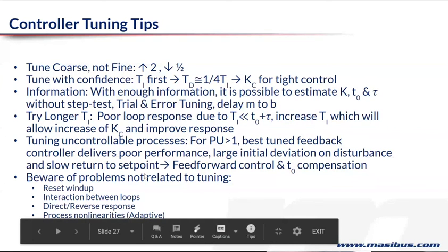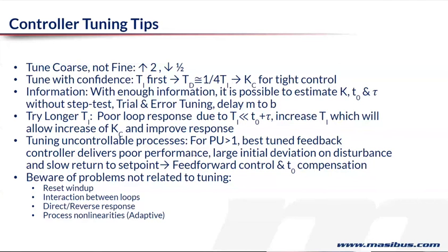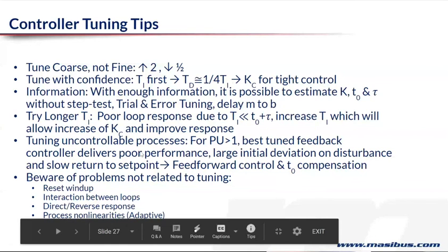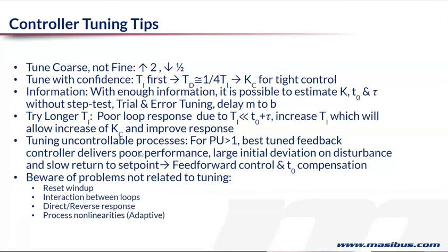Or as I said, you may need a feed forward control, or you may have to bring in the derivative term to some extent to compensate for this dead time. It is very important to understand that the more the dead time, the poorer the performance you will get from your PID controller. Whenever, suppose the flow rate of the media changes suddenly, then you will see a huge deviation and it will take a long time to come back to the set point.